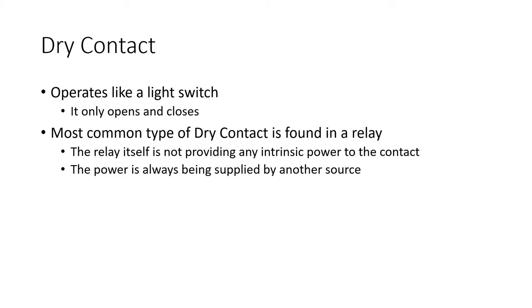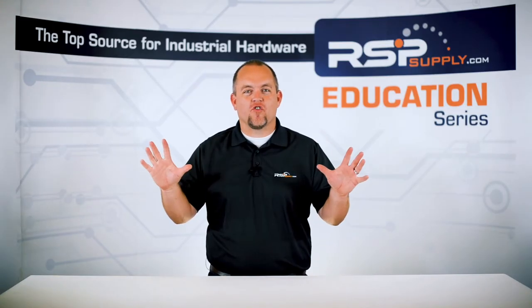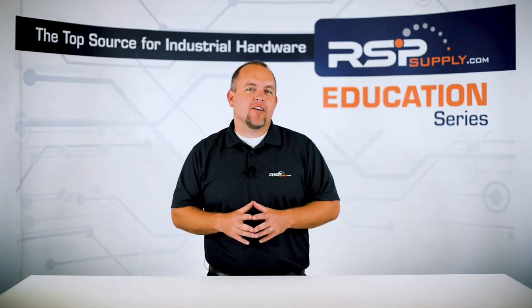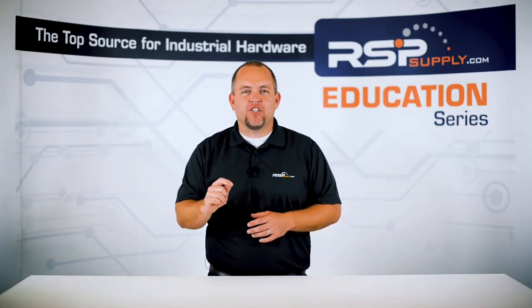One of the most common use cases of this type of contact is found in a relay. Relays have a coil that, when energized, will open or close a set of contacts. When the contacts are closed, power can flow through them to whatever source the power is intended for. But the relay itself is not providing any intrinsic power to the contacts — the power is always being supplied by another source. This is a dry contact, and they are used all over the place, especially in areas where control and automation are being used.